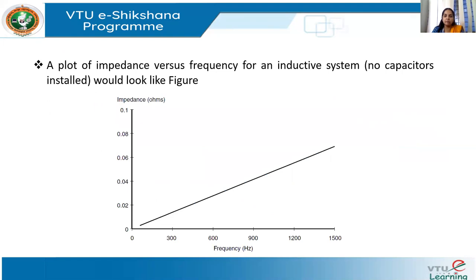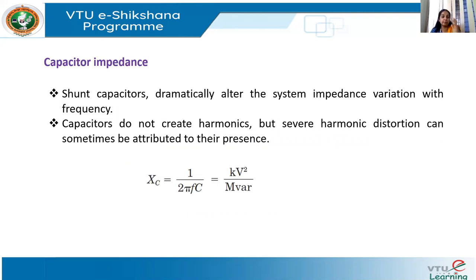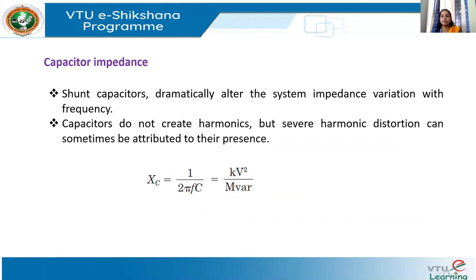The curve showing variation of impedance with respect to frequency shows it is almost linearly varying for an inductive system with no capacitance. However, when capacitance is present — for example, shunt capacitance from capacitor banks — it can dramatically alter the system impedance variation with frequency. Capacitors do not create harmonics themselves, but they can cause severe harmonic distortion affecting system performance.